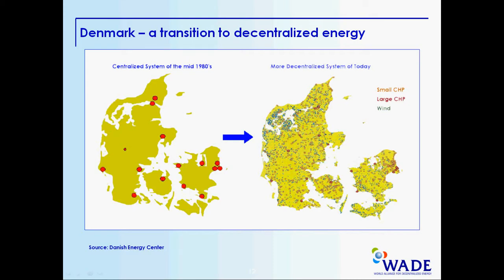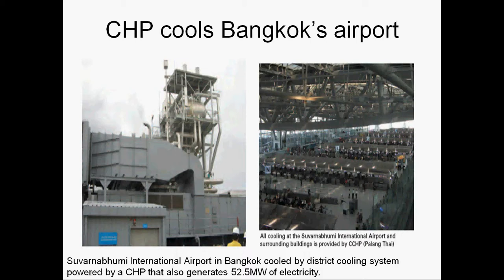In Thailand, one interesting decentralized power project that many of you have experienced is the 52.5 megawatt combined heat and power project at Suvarnabhumi Airport in Bangkok. The power plant makes electricity for the airport and also exports electricity to the grid. The waste heat from electricity generation powers a lithium bromide absorption chiller that cools the entire airport. This project was built as a joint project between EGAT, MEA, and PTT — the Petroleum Authority of Thailand — all huge state-owned companies. Since they own the grid and the gas supplies, this project didn't require a lot of government policies. The challenge is how to come up with policies that allow regular customers to implement decentralized generation.